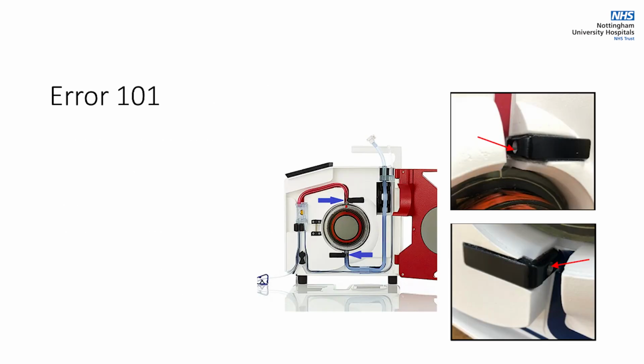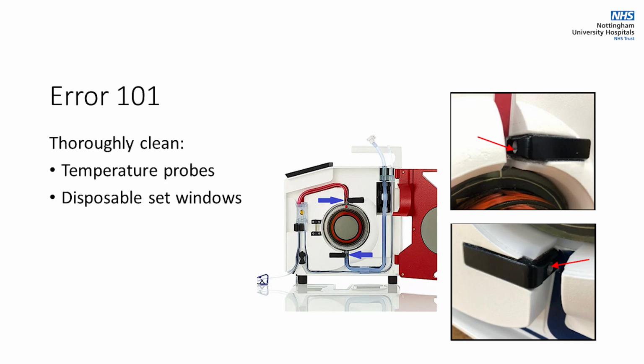Error 101. In the event of Error 101 occurring during device use, thoroughly clean temperature probes and disposable set windows before each use with a moistened cotton bud and thoroughly dry afterwards. The blue arrows show the location of the two temperature probes. The red arrows show the temperature probe holes that should be cleaned and dried if an Error 101 alarm occurs. If the error persists, clean the sensor as indicated by the blue arrow with a cotton bud and dry.